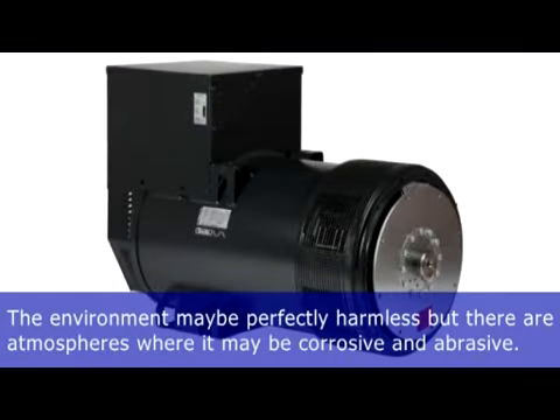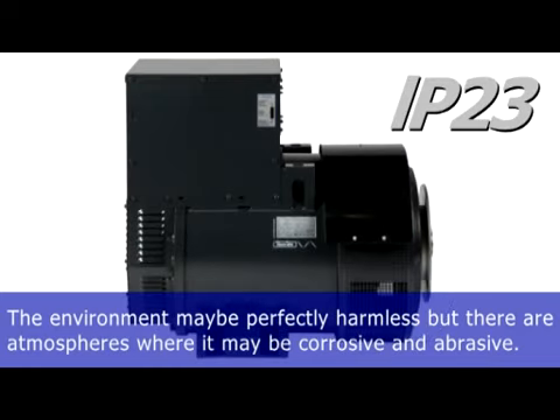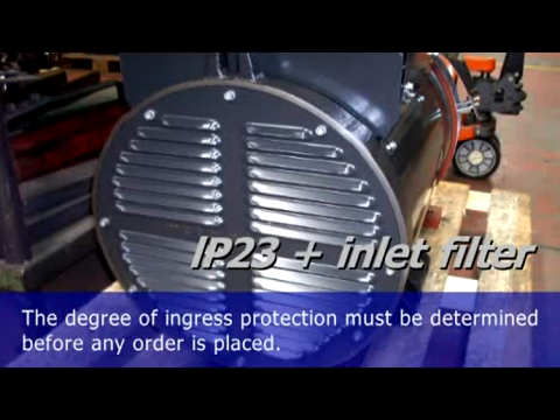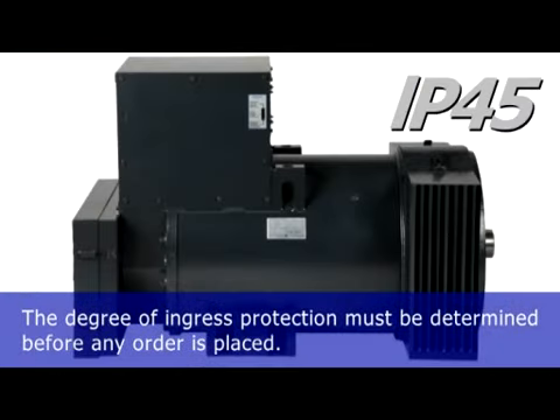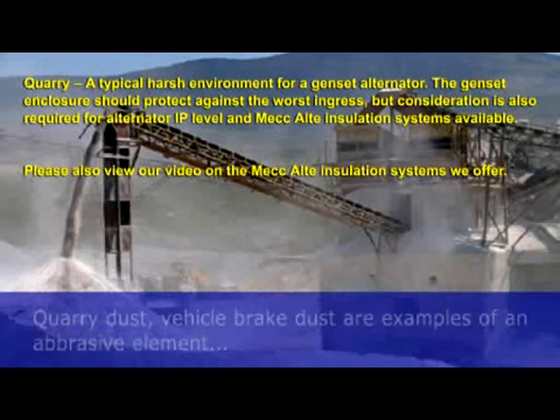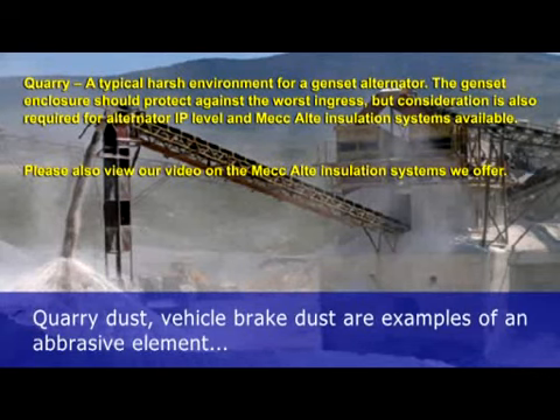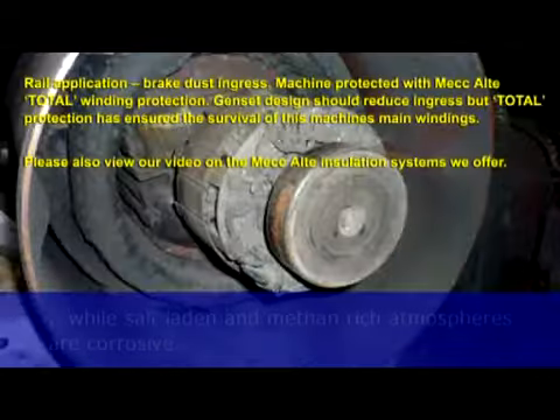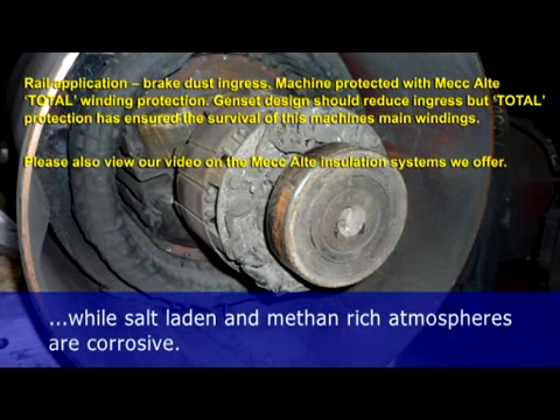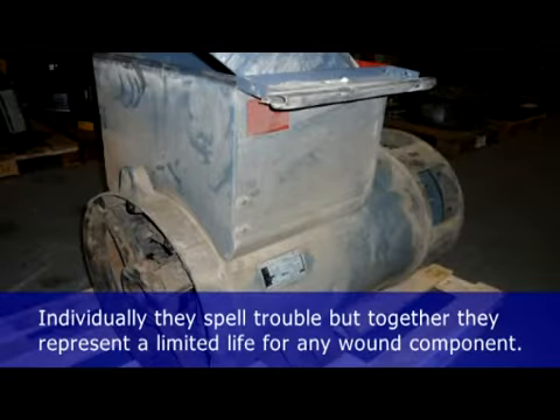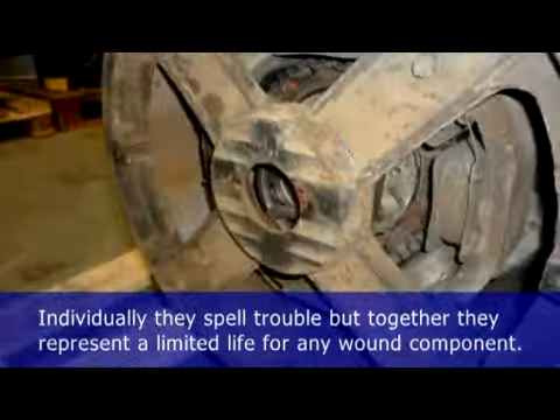The environment may be perfectly harmless, but there are atmospheres where it may be corrosive and abrasive. The degree of ingress protection must be determined before any order is placed. Quarry dust, vehicle brake dust are examples of an abrasive element, while salt-laden and methane-rich atmospheres are corrosive. Individually they spell trouble, but together they represent a limited life for any wound component. Selection of ingress protection and level of insulation is very important.